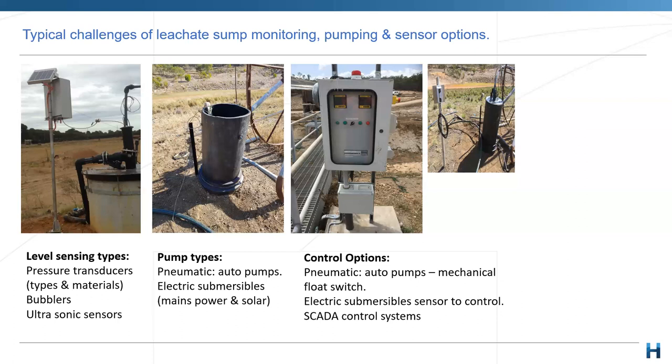On the second one, there's a pump pipe. So normally we have pneumatic pumps in the landfill, like a big landfill. Normally they have all this infrastructure ready. They've got power, they've got big compressors to run all these pneumatic pumps, air well pumps typically. So there are big landfill sites, and there's no problem to install those pumps. But we did encounter quite a number of small landfill operators, run by council, with closed landfills. They don't have power, so they can't really run a big compressor to power up the air well pump. So what we did install was a solar pumping system. We run the pump off solar power.